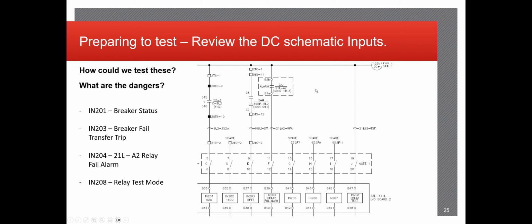Again, the relay fail alarm, like we talked about: if this relay is in service, you can't test it, because if you issue a relay fail from this relay, most likely it's going to operate every single piece of equipment that may be connected to it. So as long as it's out of service, you're good. Otherwise, it might be worthwhile looking at a different way to test.